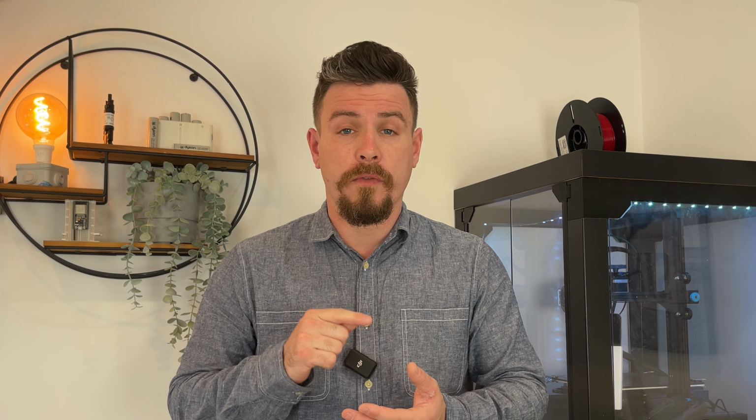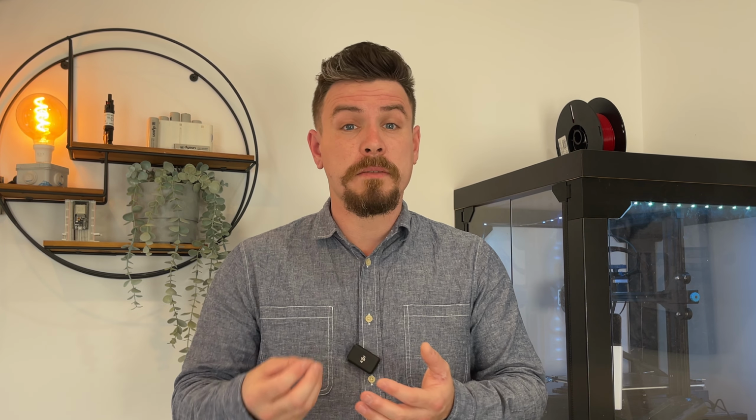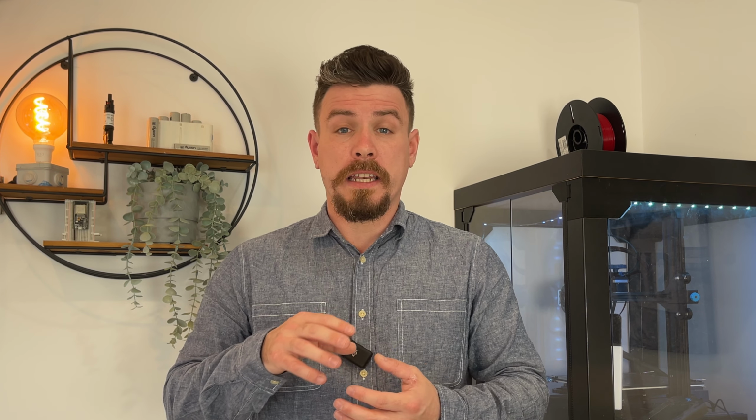First, we need to find our Ze. We're going to presume that we've gained this from our supplier, which we can do. So I'm going to use the maximum value for the TN-C-S system of 0.35 ohms, and then we'll add that to our R1 and R2. And we can get these from the book in milliohms per meter.